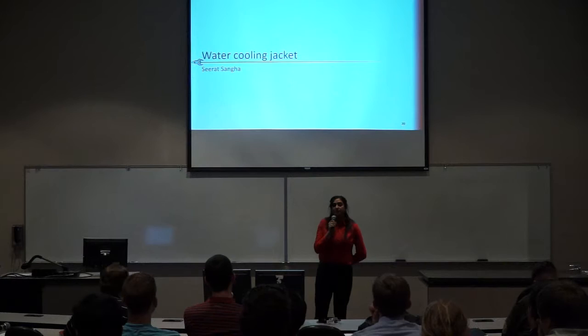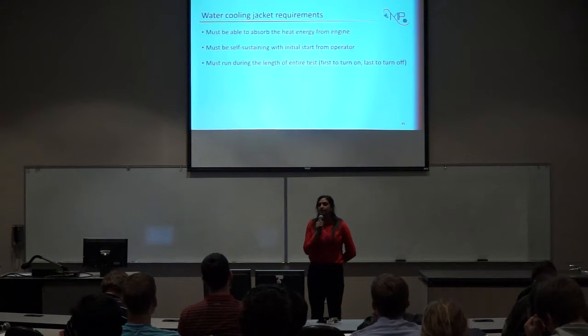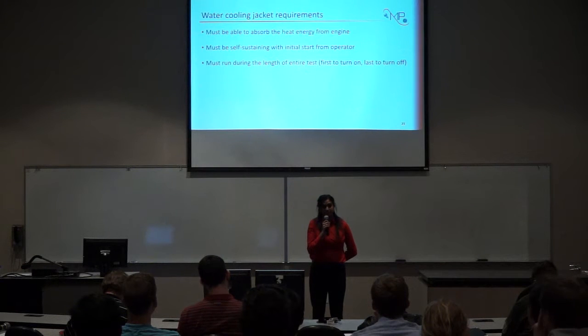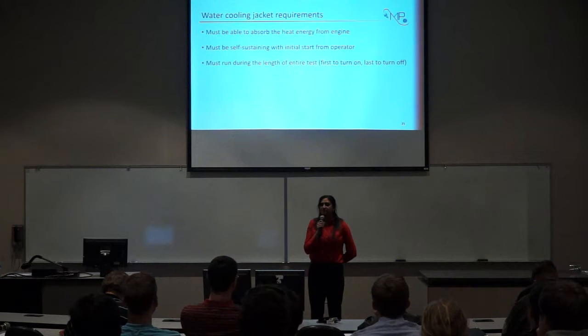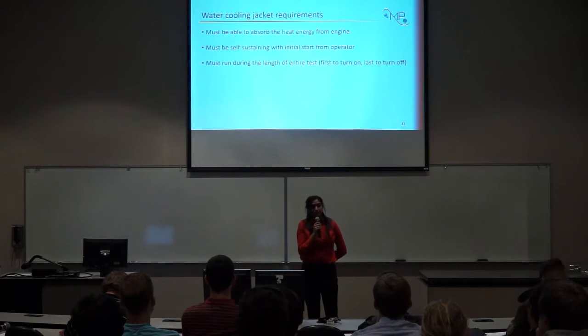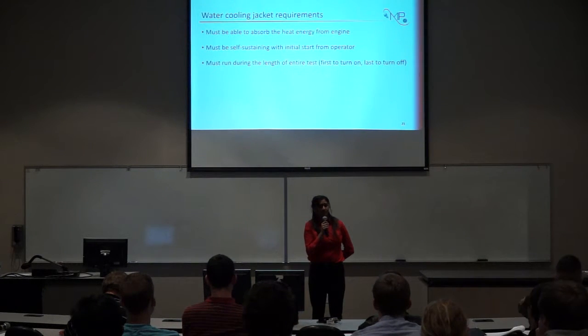Starting into the second component now, the water cooling jacket. As mentioned earlier, the cooling jacket must be able to absorb the heat energy expected from the engine. It must be self-sustaining with the initial start from the operator, and it must run through the entire duration of the test, meaning it is the first component to turn on and the last component to be turned off.